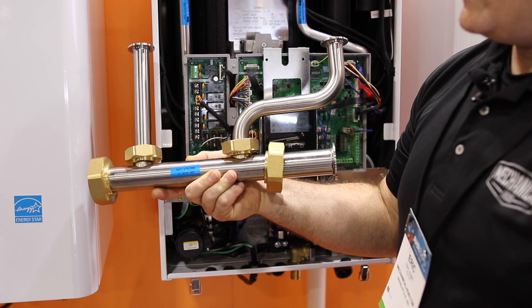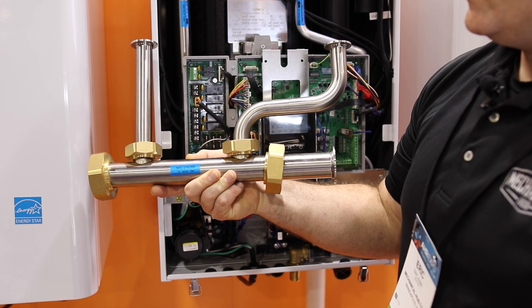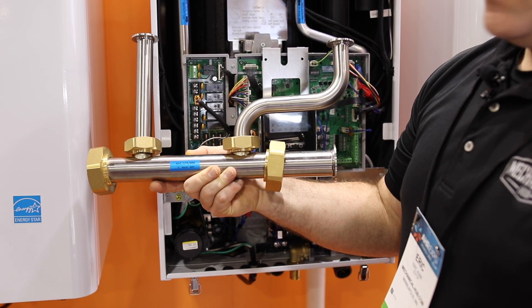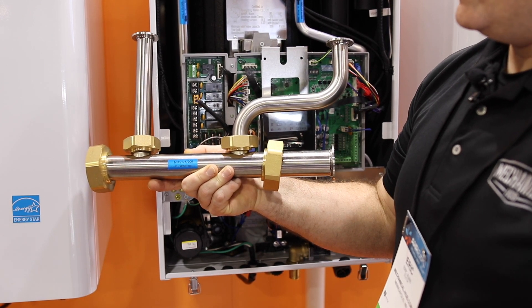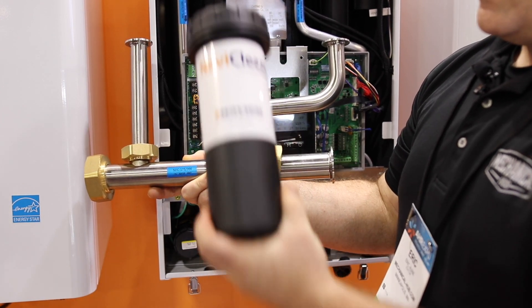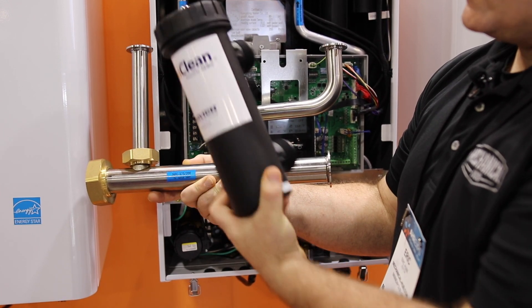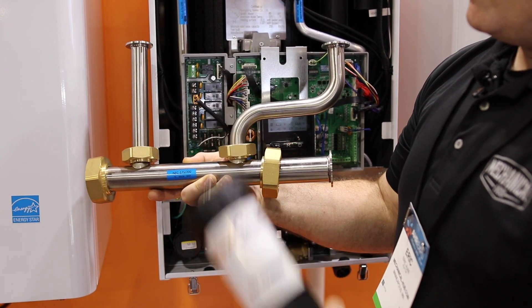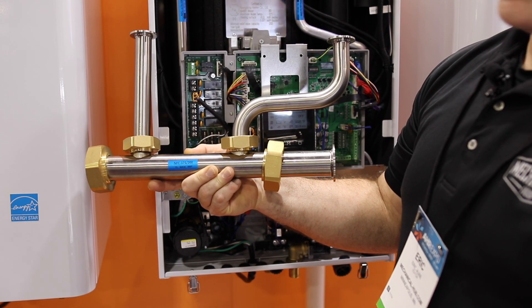Also included with the NFC is a stainless steel manifold that Navien is manufacturing. It's going to have service valves along with union fittings so it mates directly up onto the bottom of the NFC, and also the NaviClean magnetic filter. This is going to be integral in keeping the boiler operational and free of any magnetic debris like iron oxides.